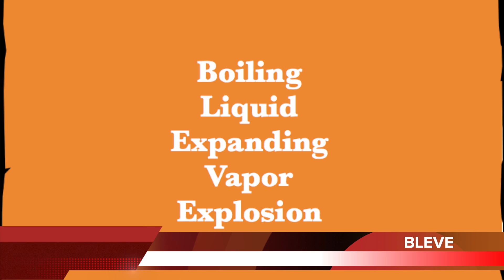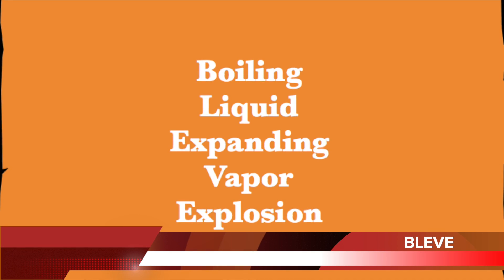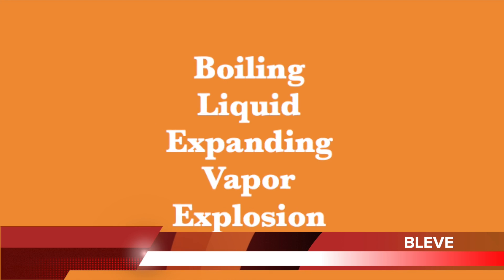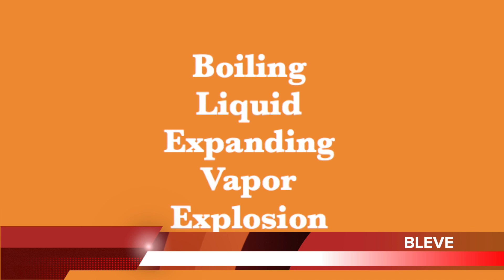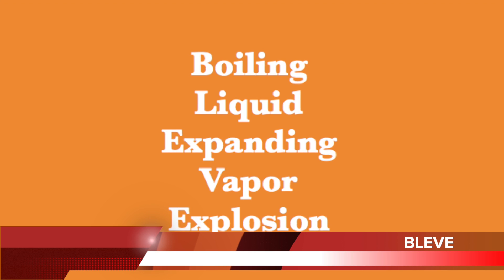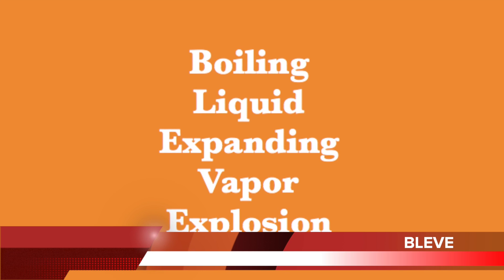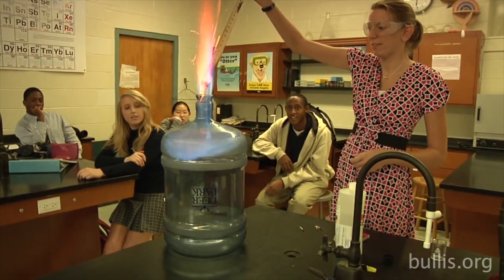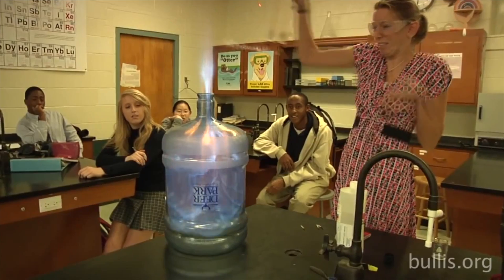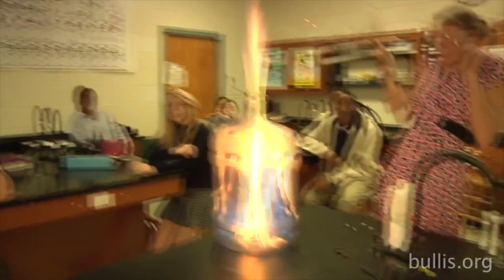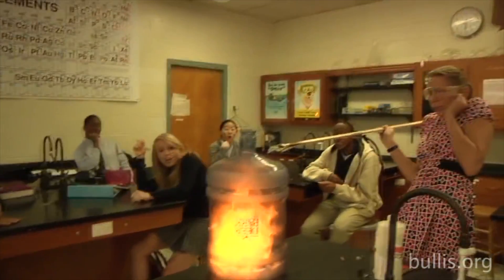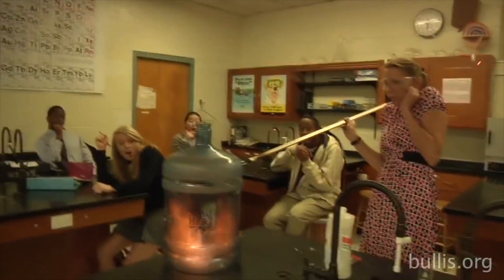BLEVE is a boiling liquid-expanding vapor explosion, resulting when a container of flammable liquid is exposed to high heat and the internal pressure produced becomes so great that the integrity of the container eventually fails, resulting in a release of vapors that ignite in a very violent explosion. If this flammable vapor cloud finds an ignition source, and the vapor concentration is within flammable limits, then the rapidly expanding cloud will burn, probably explosively.